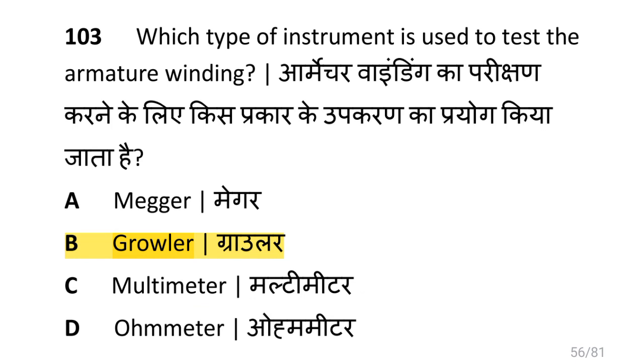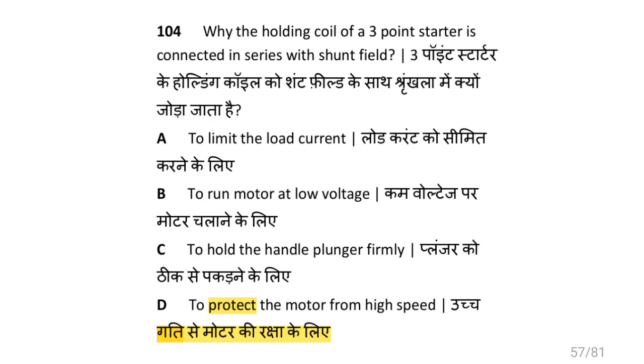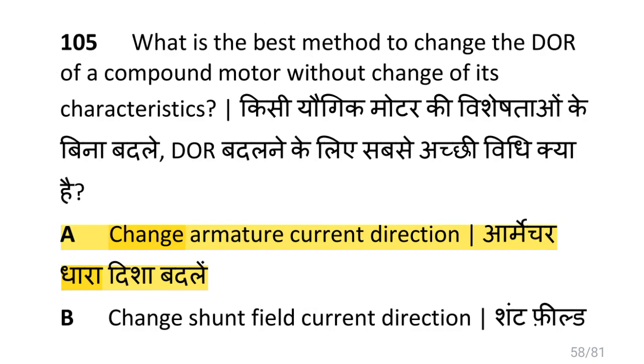Which type of instrument is used to test the armature winding? That is a growler. Why is the holding coil of a 3 point starter connected in series with shunt field? That is to protect the motor from high speed. What is the best method to change the direction of rotation of a compound motor without changing its characteristics? That is to change the armature current direction.